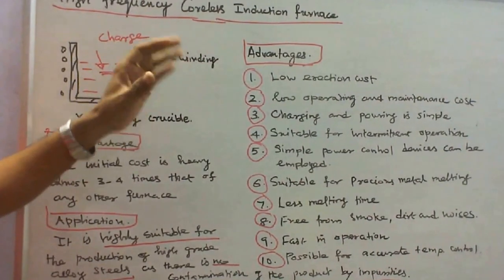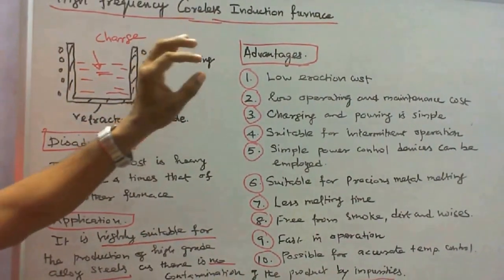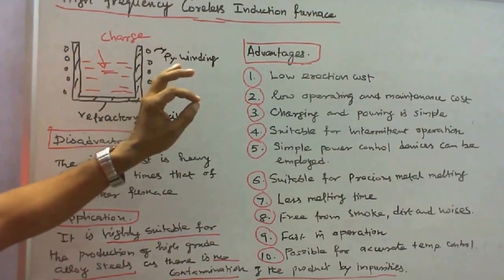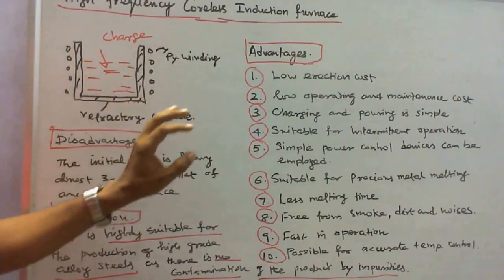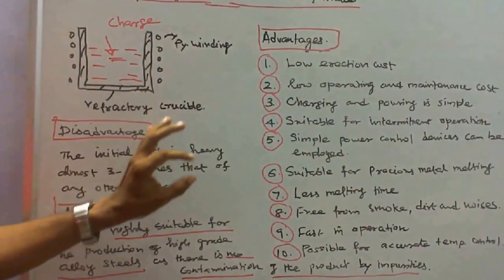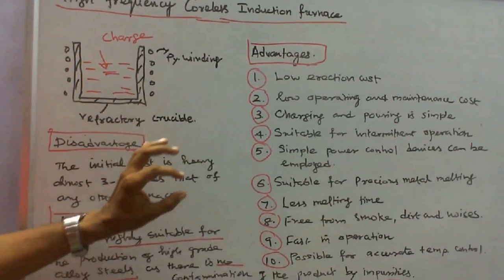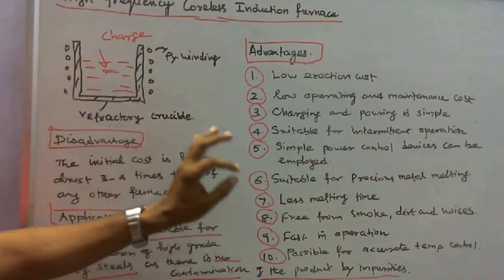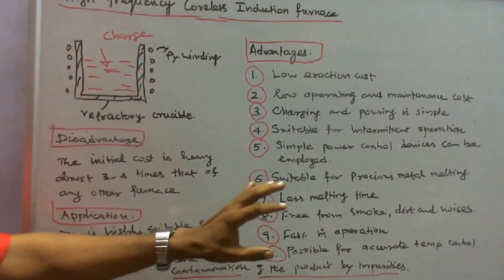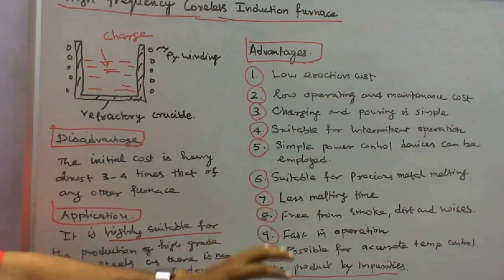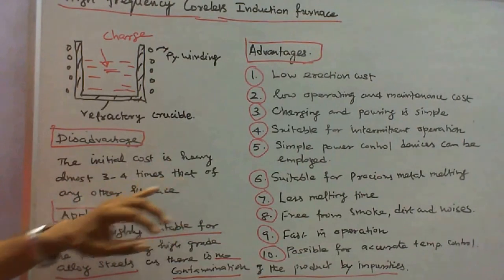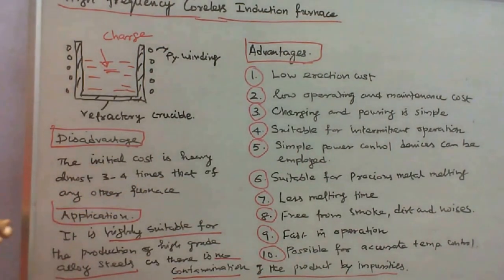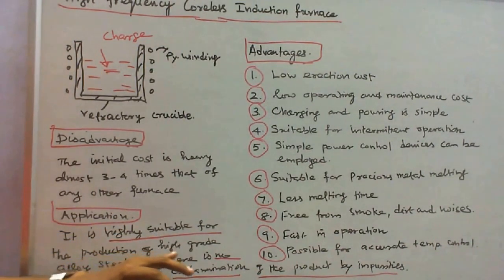The advantages of coreless induction furnaces are: 1. Low erection cost; 2. Low operating and maintenance cost; 3. Charging and pouring is simple; 4. Suitable for intermittent operation; 5. Simple power control devices can be employed; 6. Suitable for precious metal melting; 7. Less melting time; 8. Free from smoke, dirt and noise; 9. Fast in operation; 10. Possible for accurate temperature control. The disadvantage is that the initial cost is heavy — almost 3 to 4 times that of any other furnace. The application is that it is highly suitable for the production of high-grade alloy steel, as there is no contamination of the product by impurities.